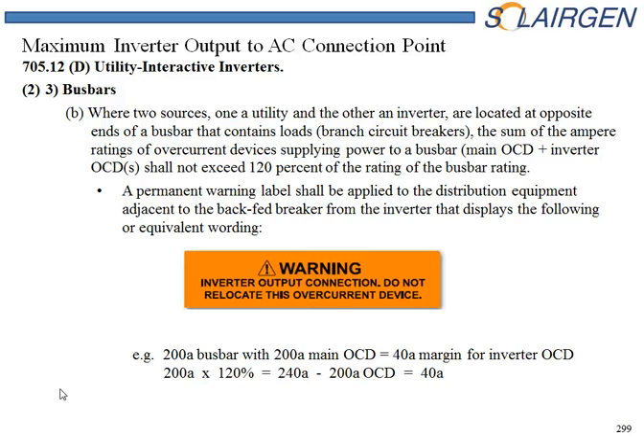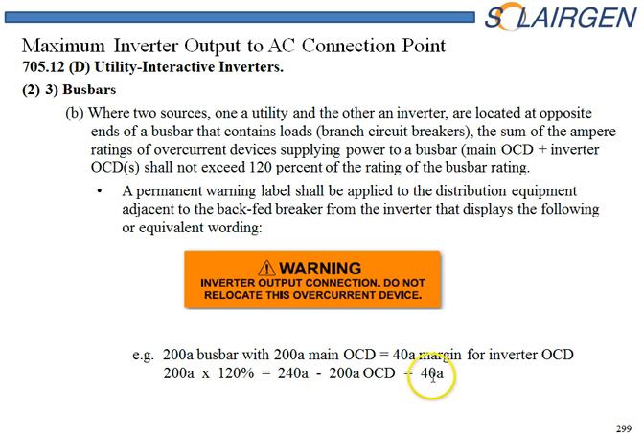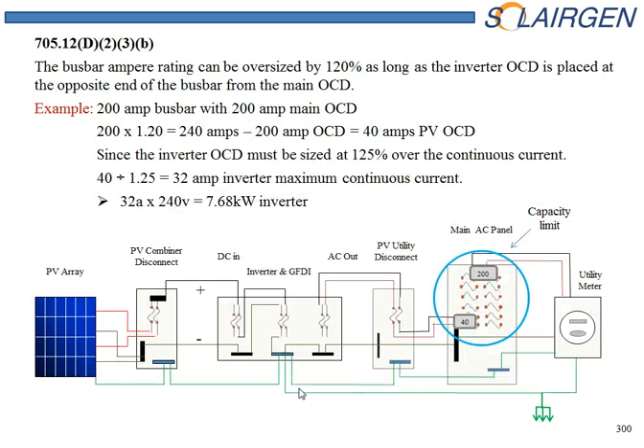The first rule allows us to connect into the main panel by placing the inverter overcurrent device at the opposite end of the main overcurrent device, or the main feed coming in from the utility. That way we're feeding two different directions and not overheating the bus bar. In this case, they want us to put a label right next to the breaker, and this breaker goes to the bottom of the panel. The bus bar cannot be oversized by more than 120% — the main overcurrent device plus the inverter overcurrent device cannot exceed 120%, which in this case is 240 amps. Here we see a line diagram representing that calculation, and we are in good compliance with the code.